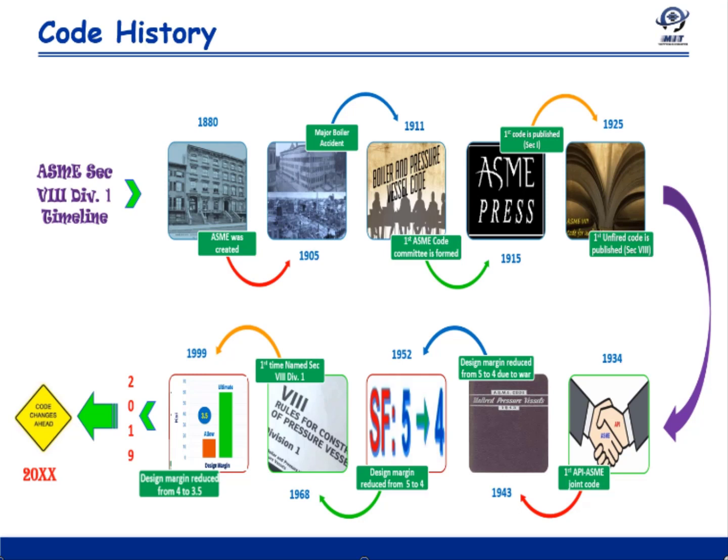During the Second World War, the need to conserve material led ASME to revise the safety factor from the original 5 to 4. This was considered a temporary change only for the duration of the war, after which it was expected to revert to 5. But after the war, the safety factor was finally revised permanently from 5 to 4 after due consideration.